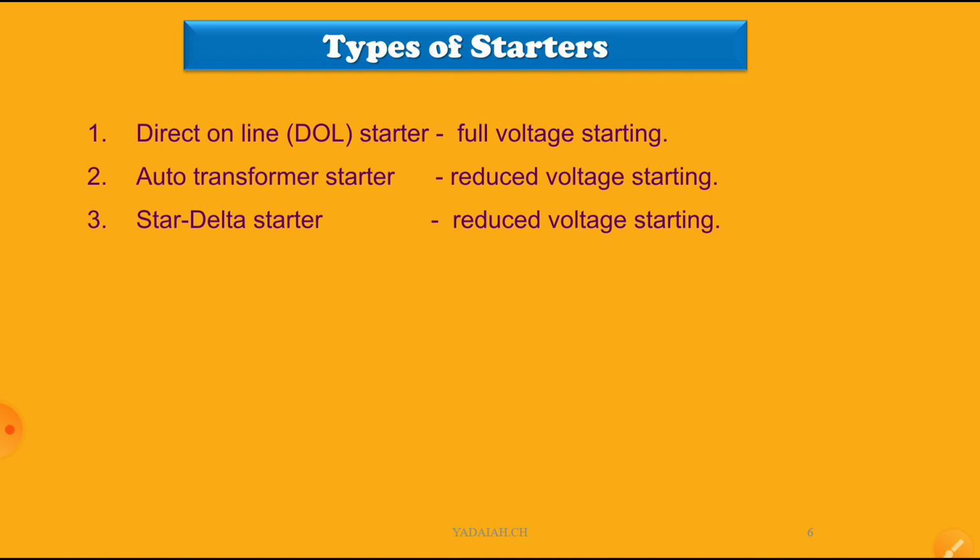As we know, in case of star connection, the phase current and line current are the same, but the line voltage is equal to root 3 times the phase voltage. That means if it is connected in star, the 400 volts initially is forcefully converted to 400 by root 3, that is 231 volts, given to the motor. So reduced voltage is given to our motor.